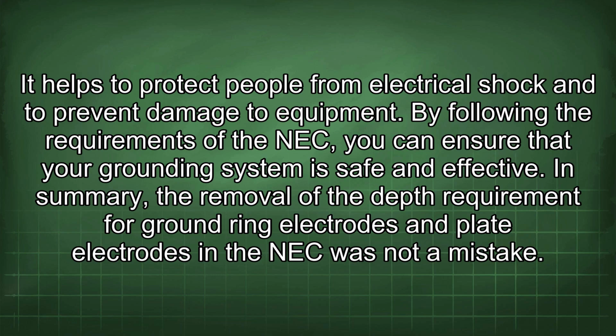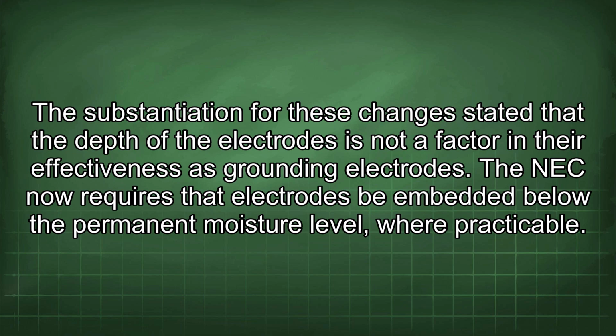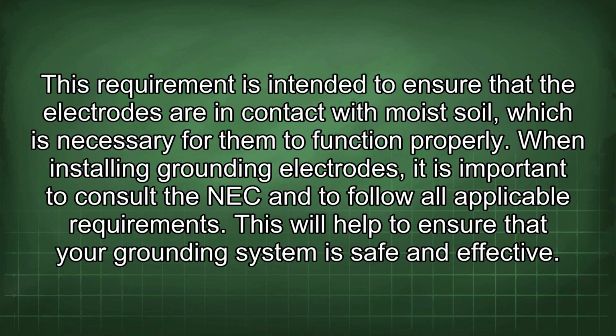In summary, the removal of the depth requirement for ground ring electrodes and plate electrodes in the NEC was not a mistake. The substantiation for these changes stated that the depth of the electrodes is not a factor in their effectiveness as grounding electrodes. The NEC now requires that electrodes be embedded below the permanent moisture level where practicable. This requirement is intended to ensure that the electrodes are in contact with moist soil, which is necessary for them to function properly. When installing grounding electrodes, it is important to consult the NEC and to follow all applicable requirements. This will help to ensure that your grounding system is safe and effective.